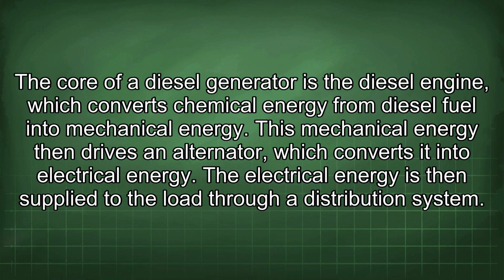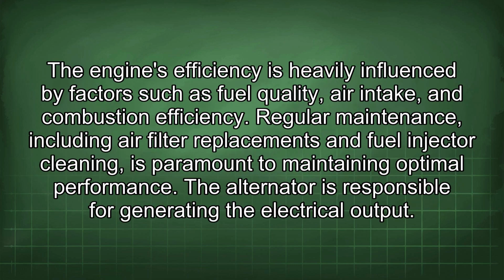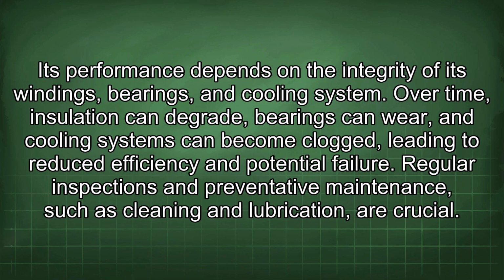The electrical energy is then supplied to the load through a distribution system. The engine's efficiency is heavily influenced by factors such as fuel quality, air intake, and combustion efficiency. Regular maintenance, including air filter replacements and fuel injector cleaning, is paramount to maintaining optimal performance. The alternator is responsible for generating the electrical output. Its performance depends on the integrity of its windings, bearings, and cooling system. Over time, insulation can degrade, bearings can wear, and cooling systems can become clogged, leading to reduced efficiency and potential failure. Regular inspections and preventative maintenance, such as cleaning and lubrication, are crucial.